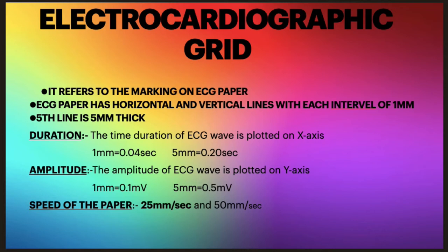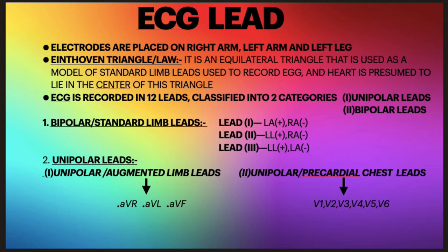Regarding the speed of the paper: there are two speeds — 25 mm per second and 50 mm per second. The 25 mm per second speed is mostly used, but if the heart rate or rhythm is very fast, then we use the 50 mm per second speed.